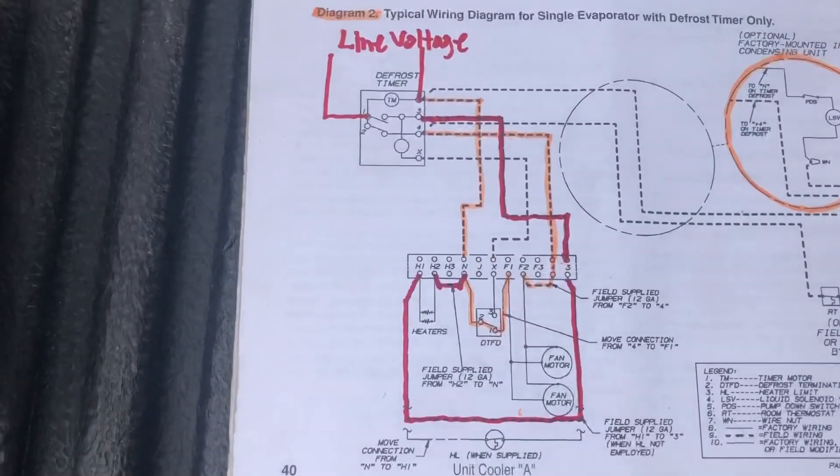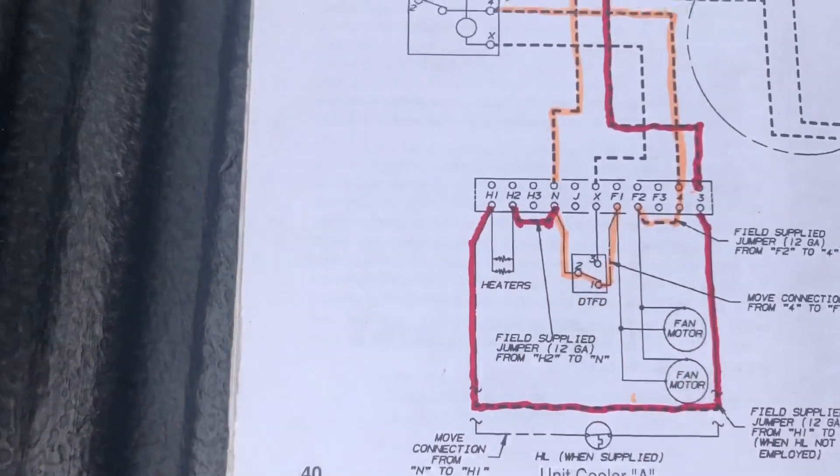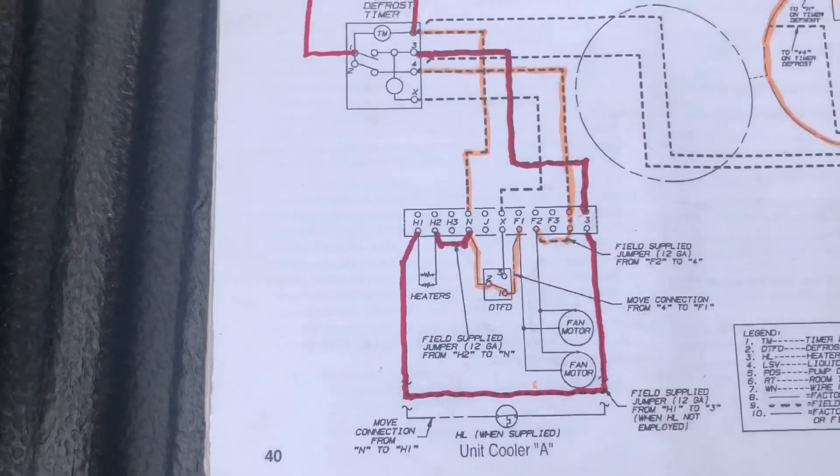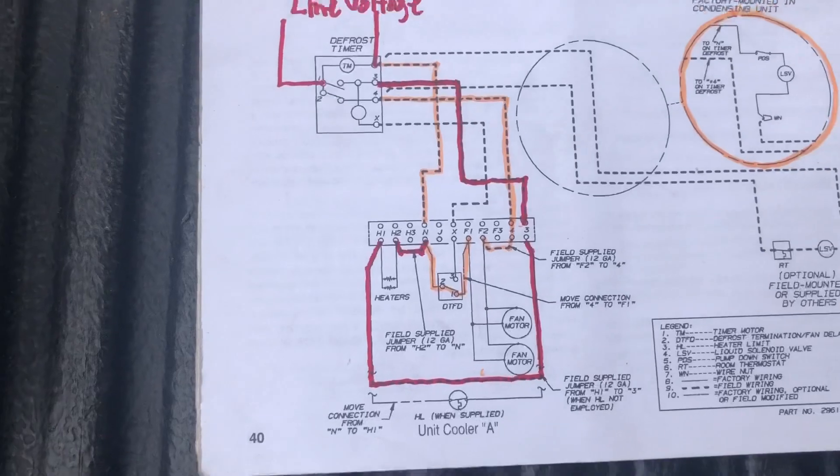Sometimes it's really confusing if this defrost termination is bad, you don't know your fans aren't coming on. But normally all you do is jump out this here, the 2 and 1 on it, which would be the red and your black wire. That's how you can diagnose that to see if your fans will work.